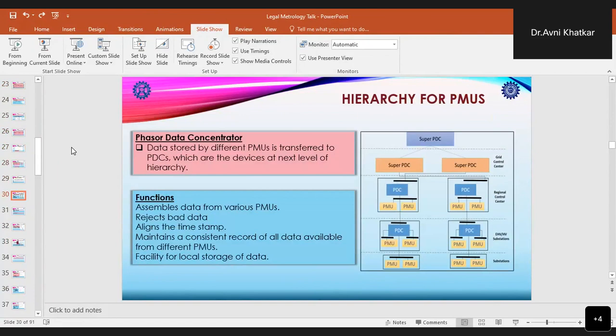Now, as per this architecture, at the substations these PMUs are installed, and they provide the information of the substations to the PDCs. PDCs are nothing but phasor data concentrators, and they store the data made available to them by the different PMUs. These PDCs are the devices at the next level of hierarchy to the PMUs. The major function of these PDCs is to assemble all the data available to them from the various PMUs, reject any bad data, align the timestamps if there is any mismatch, and maintain a consistent record of all the data from different PMUs. These PDCs also have a facility for local storage of data.